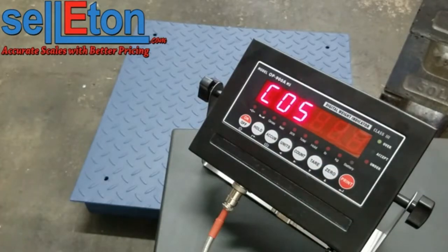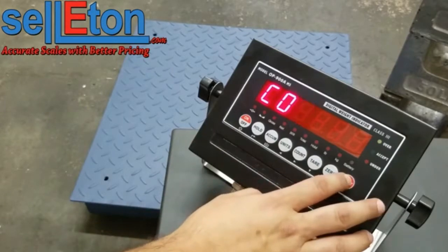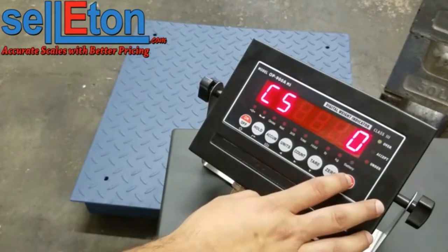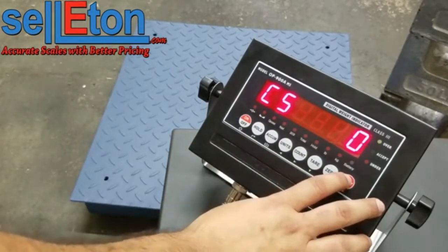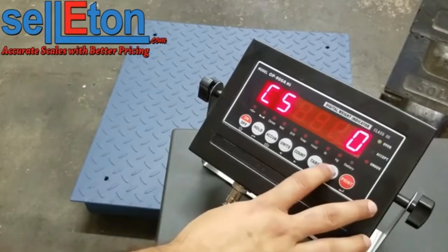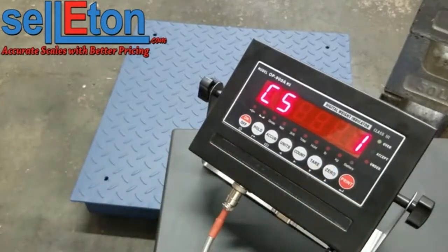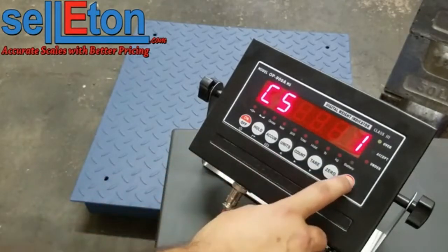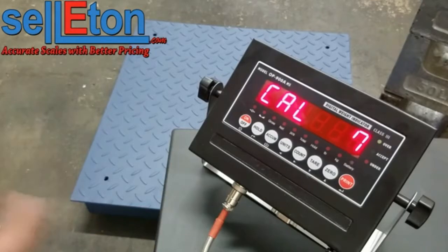We will enter C05, and here we press enter one more time and change this to 1. We want the scale to clear everything out to start calibration, so we press print, and it does a countdown all the way down to 0, and it clears.